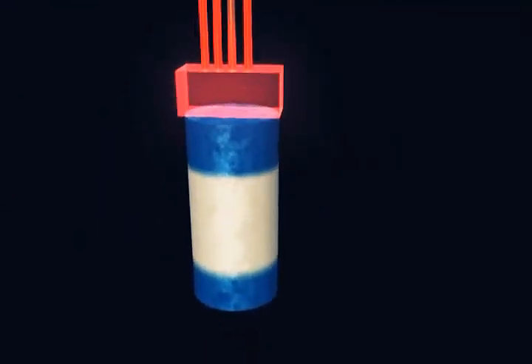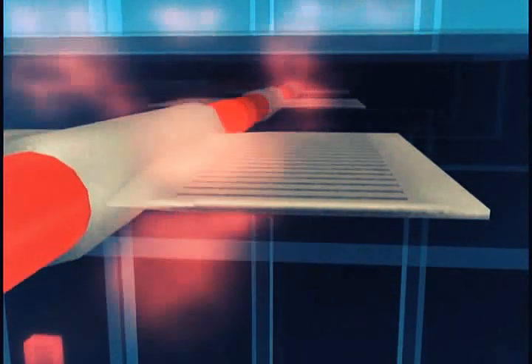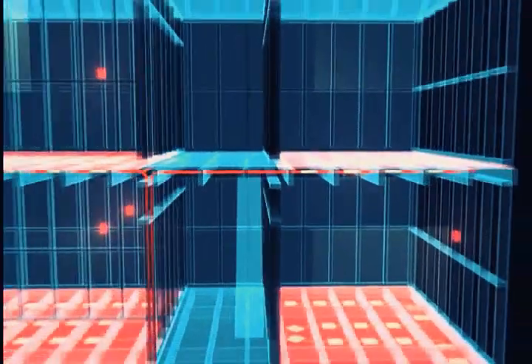the floors. Within those joist spaces, the hot water's heat is conducted to lightweight louvered aluminum plates attached to the tubing called Ultrafins. The Ultrafins radiate the heat and warm the air between the joists, creating hot air convection. The hot air then warms the entire floor above it, converting it into a giant radiator which transmits comfortable, uniform heat throughout the living space above.